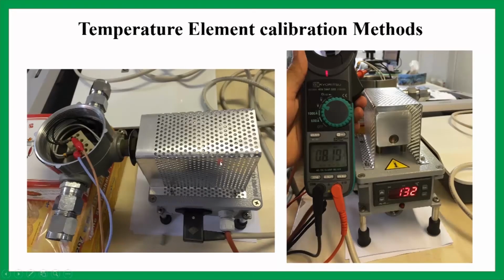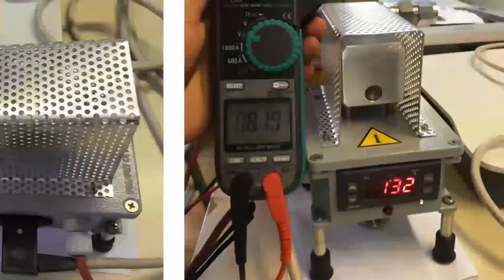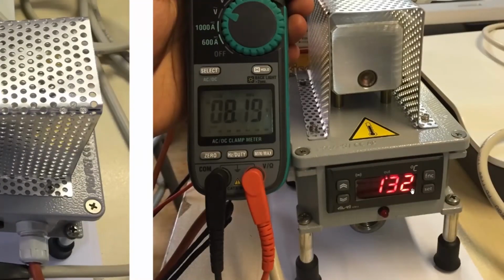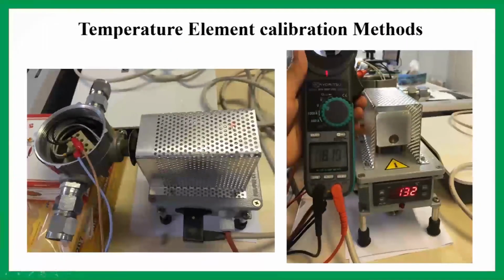Here is the way for calibration. I'm sure you could remember something about the oven. We have an oven here, and to check the device, I just put the stem inside the oven and raised, for example, the temperature to 132, then found the voltage that this device produced. So for these types of things, you can use the oven for calibration.